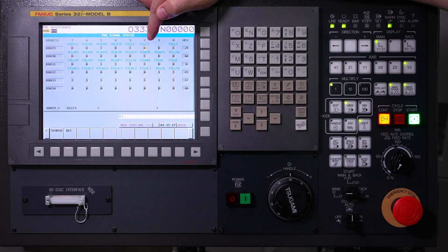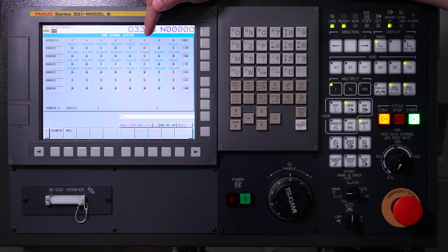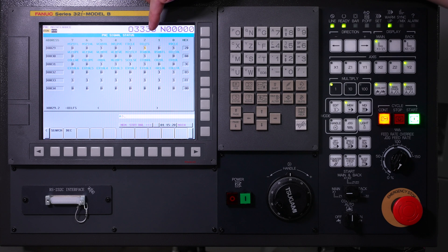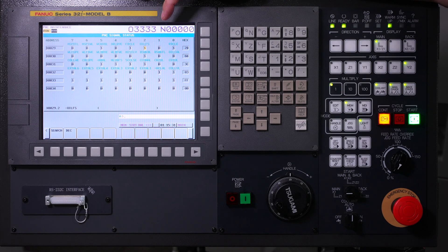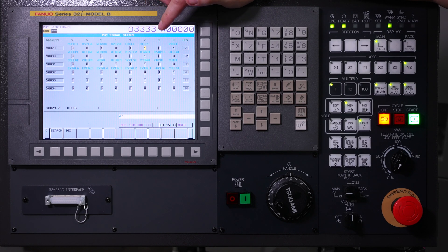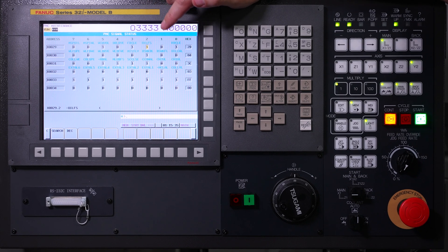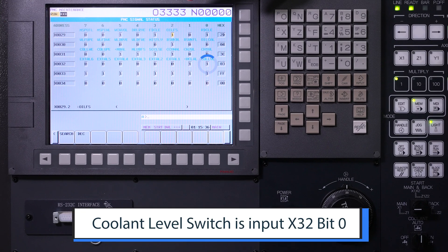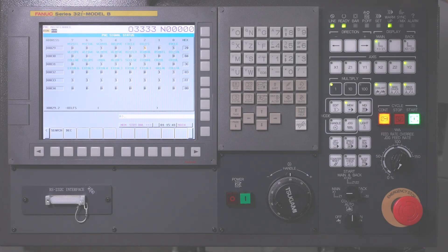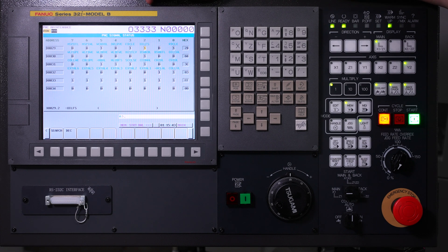Sometimes you'll get an alarm that says coolant alarm — either an EX-1010 alarm or an EX-1061 alarm. That alarm circuit on some machines, not all, is tied in with the coolant level switch. Your coolant level switch is a separate input, which is right here. As you can see, the coolant level is fine.